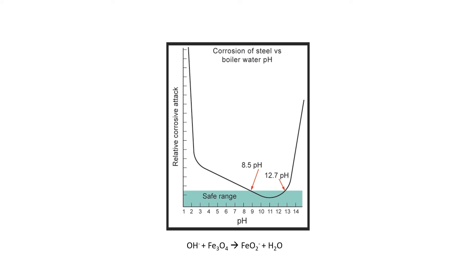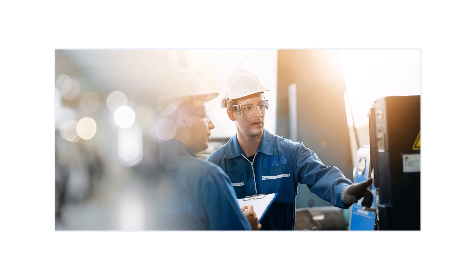Boiler water is generally considered corrosive to metal when the pH is outside the range of 8.5 to 12.7. This is clearly indicated by a curve on a graph with pH on the x-axis and relative corrosive attack on the y-axis. Generally, a typical pH range for boiler water in a high-pressure steam boiler is about 10 to 11.